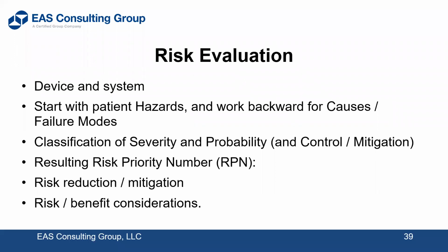I like to consider all risks ultimately down to the end user. That's the key - I'm not talking about budget risk, business risk, etc. That has to be a consideration for profitability of your company, yes, and you have to consider it. But as far as the FDA is concerned, when doing a risk analysis for your product under 14971, financial, budget, delivery time, and marketing are not considerations. Only the risk to the patient is.